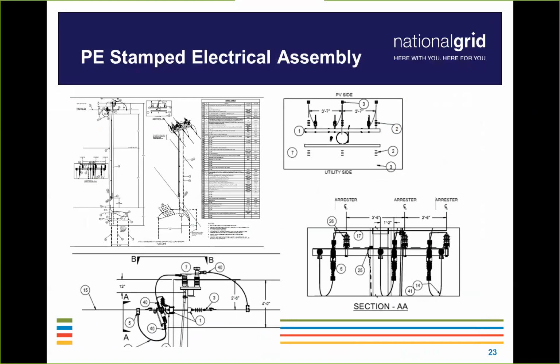And by showing that information, we can tie this back to a plan drawing view and understand in a two-dimensional space what that three-dimensional physical installation is supposed to look like. So now if you have different poles, so for example, if you have one pole that is a three-phase gang-operated switch, and then the next pole may be your overcurrent protective equipment, and another pole with the metering equipment, having an illustration for each one gives us the full detail that we're looking for in order to make sure when we look at the drawings, everything that is presented is presented in a manner and includes all the required equipment that we have for interconnections.